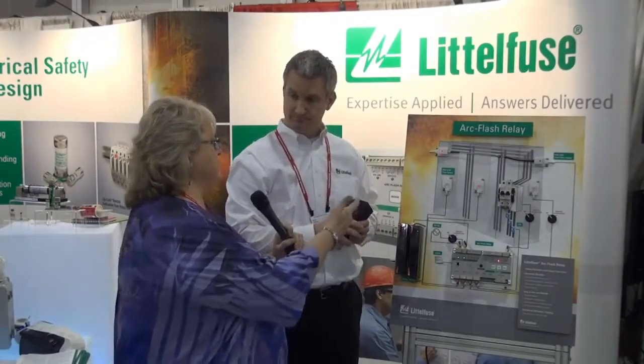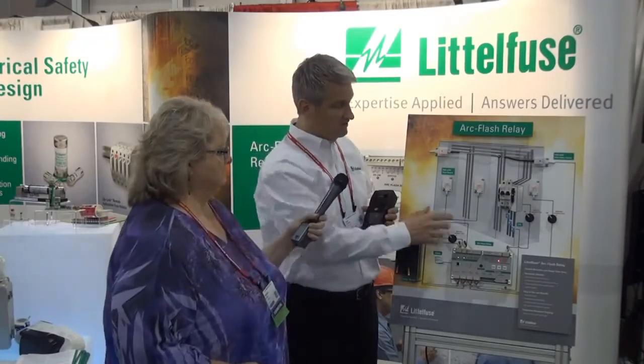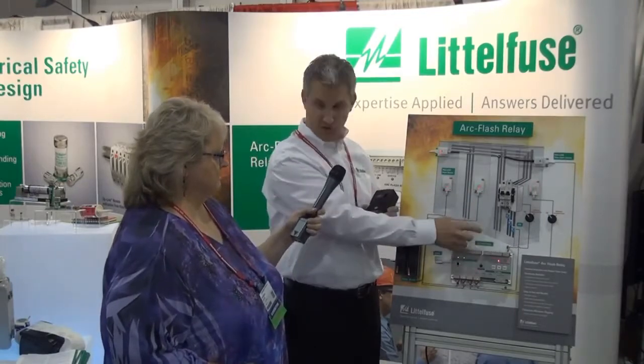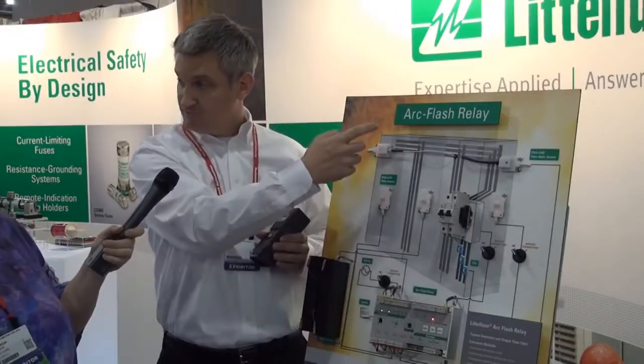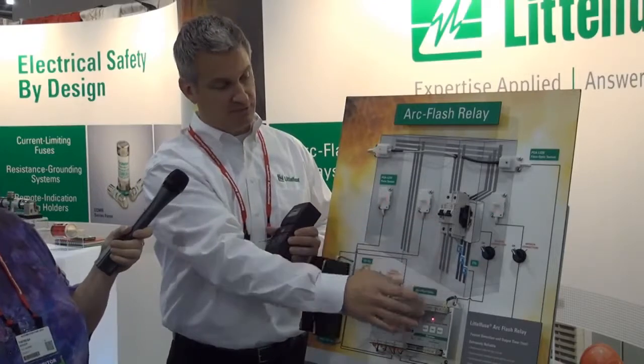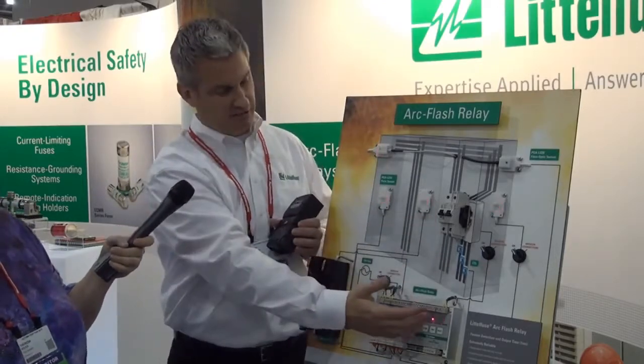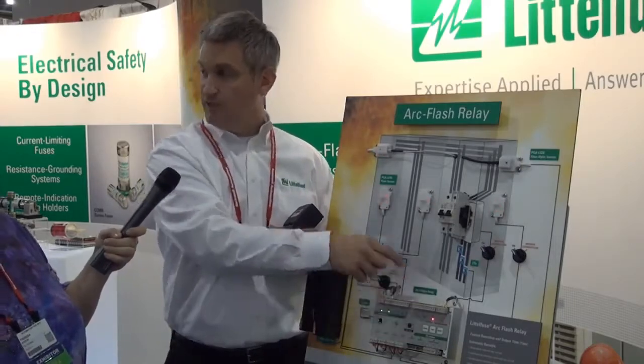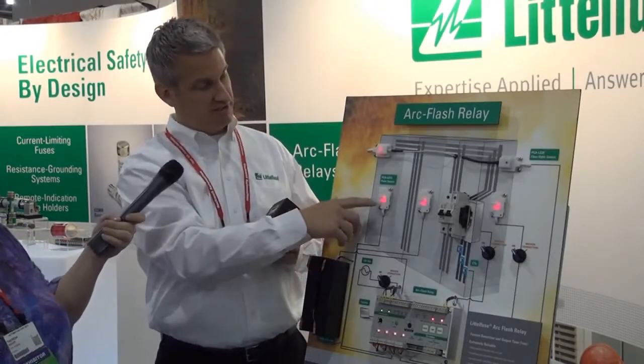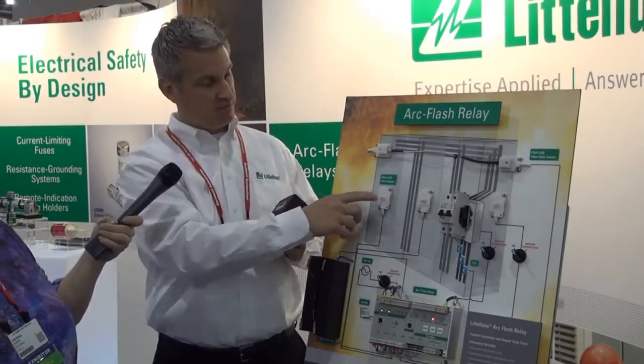Now, what happens if it doesn't trip? That's a great question. So if it doesn't trip, this actually has the ability, that's not shown here, to trip an upstream breaker. So we look for that as well. So for some reason we see an arc flash, and it creates a signal, it goes to the local circuit breaker to trip, it doesn't trip, it sends a second signal up to an upstream breaker to remove power. So again, it's an extra redundant feature built into the relay there. And you can also see here the sensors are blinking at a different rate. They're not blinking twice, two quick blinks to say that the system is okay. It's blinking one slow one. That tells you which sensor saw the fault there.